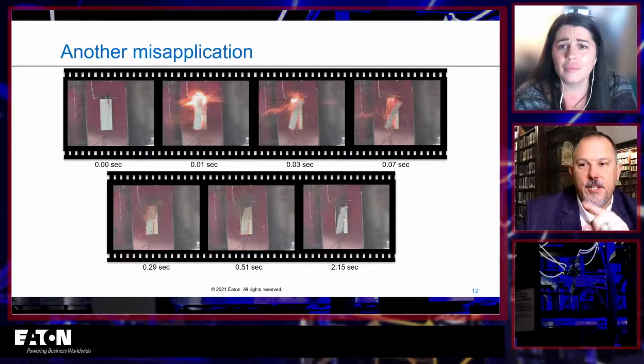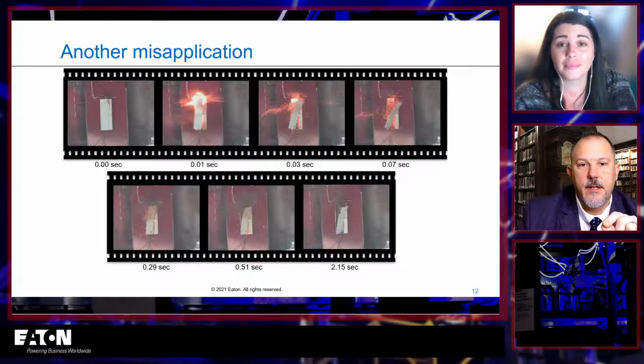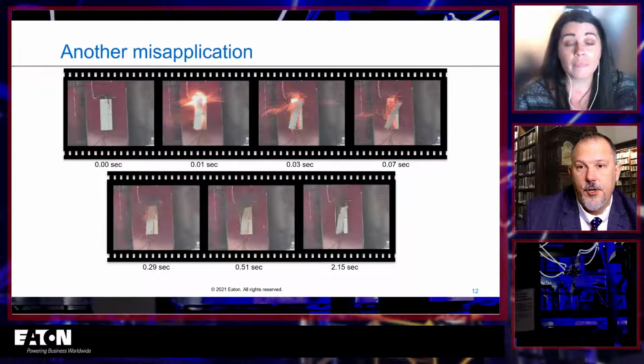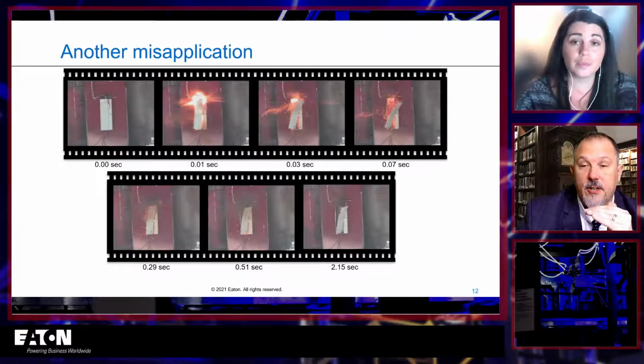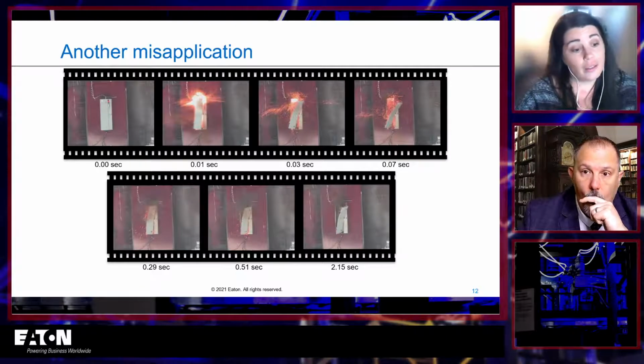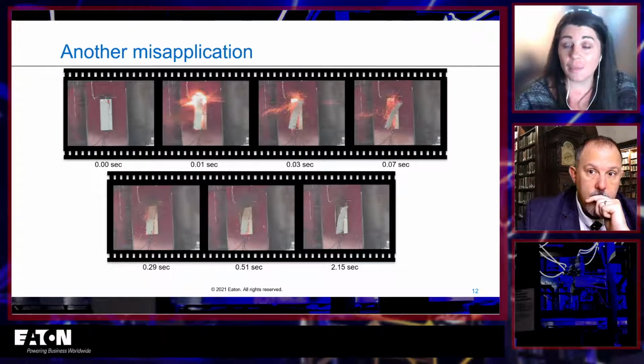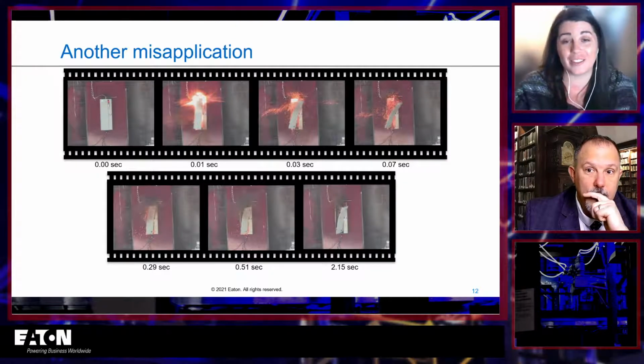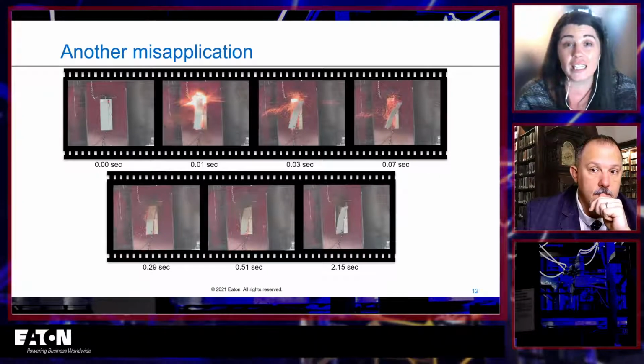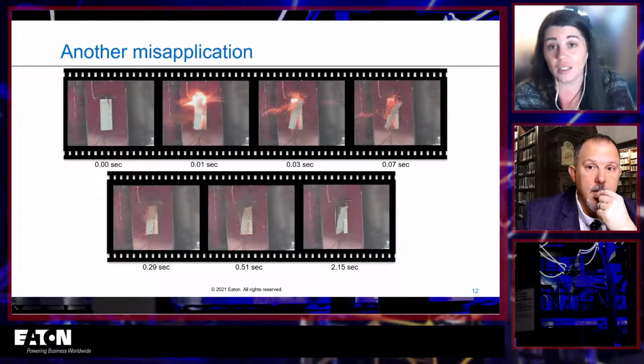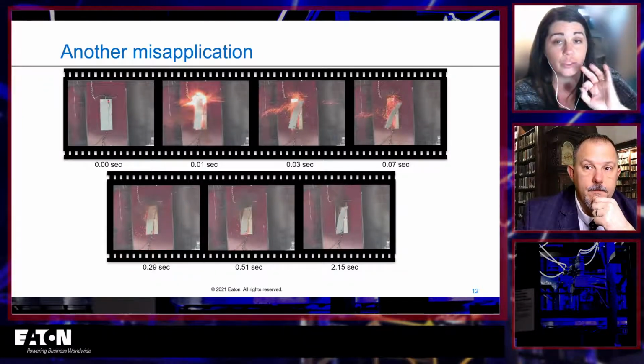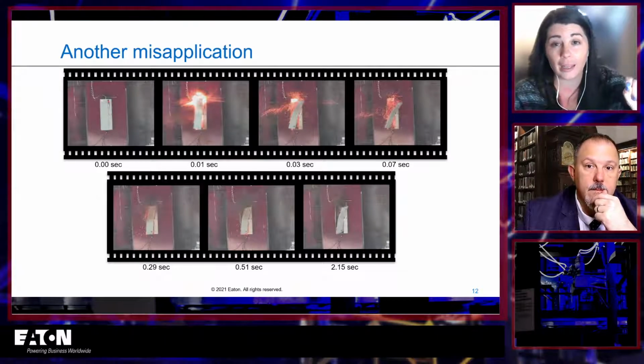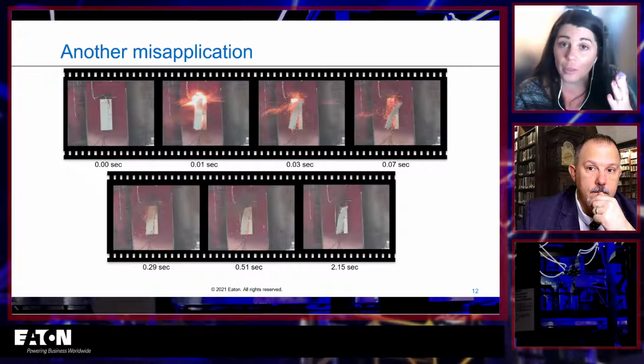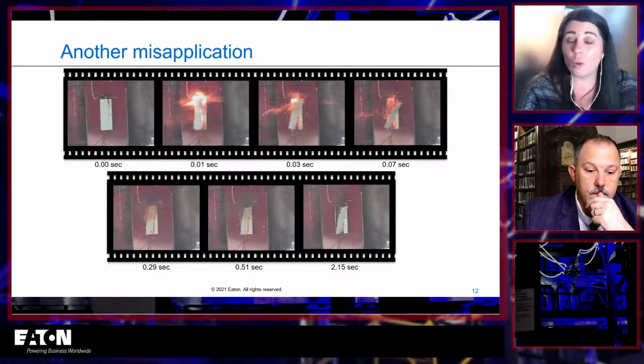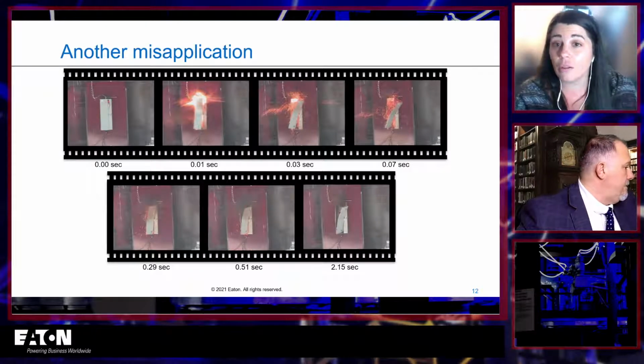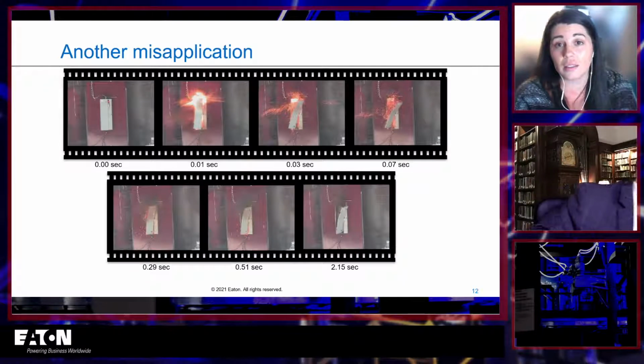Now, David Rodriguez had a question about how do you know to replace the fuse? Like you said, when a circuit breaker opens, you're going to see the handle in the off position or in the center position. What about a fuse? Well, if it's a non-indicating fuse, nothing much happens, except you should notice that you've lost power somewhere else. So that's usually your biggest indication. There are accessories and indicating fuses that exist. You can get a fuse that will change color, I believe from white to black on most of the Bussmann ones, and tell you that it has opened. So as soon as you open the panel, you'll be able to tell. Some holders or switches that the fuses go into have little LEDs that'll alert you that, hey, this is the one that's open for you.